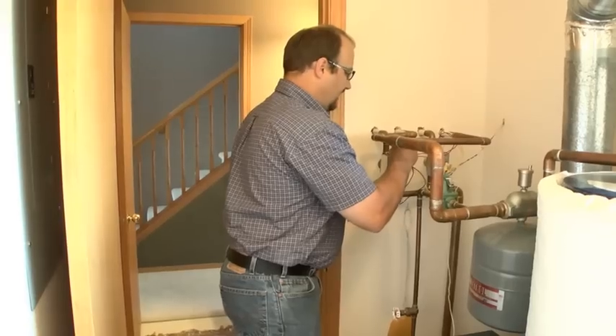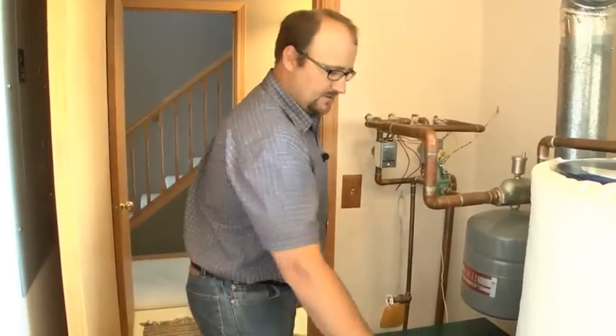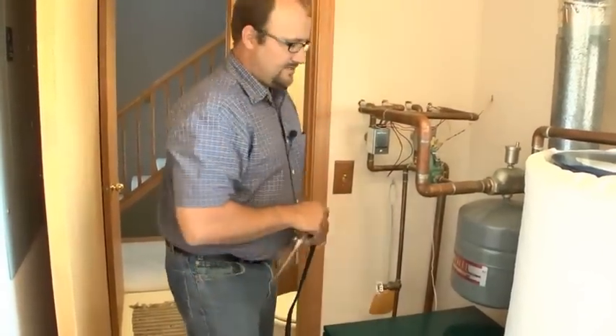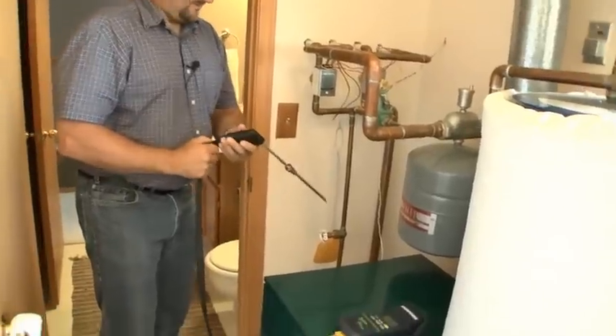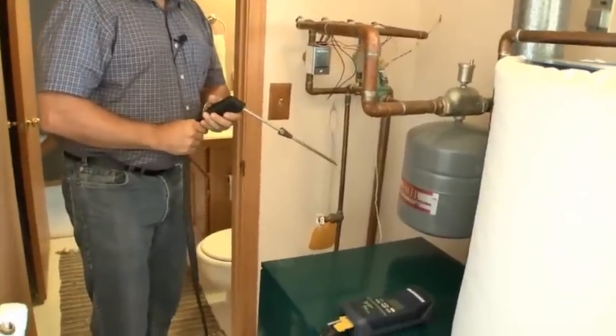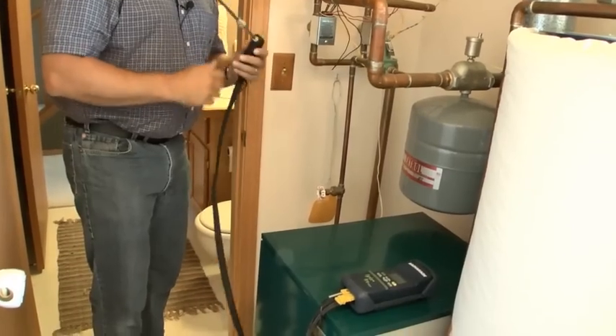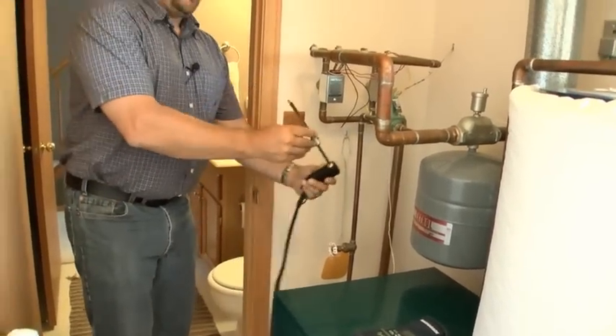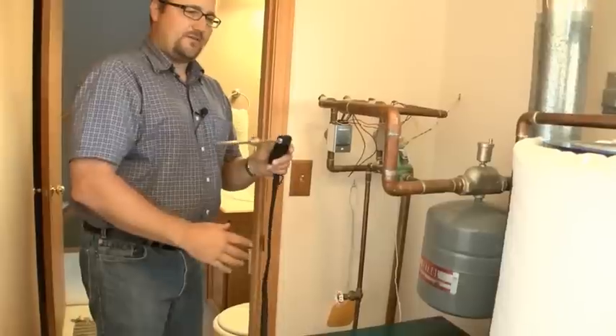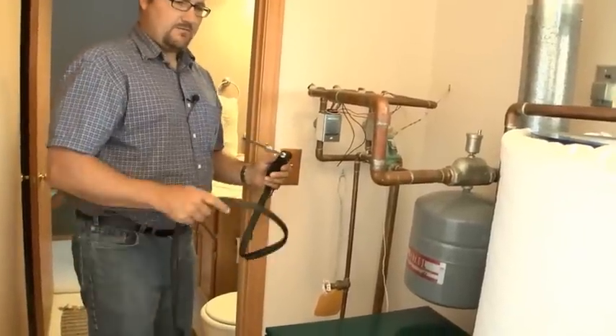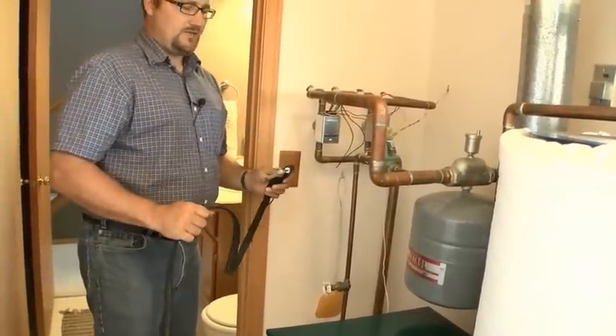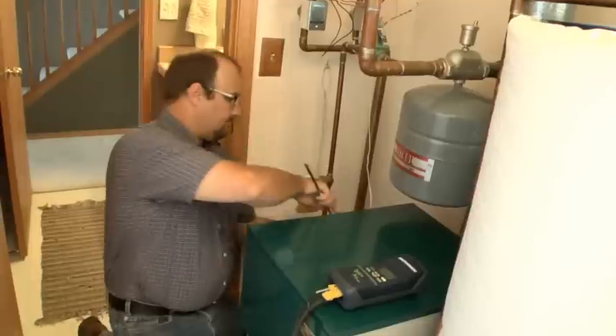And I'm just jumpering the end switch to get this thing to start. This has a draft hood. It's on the back of this boiler. It's fairly difficult to get to. I have to take this probe and get it up inside the draft hood as close to the top of the heat exchanger as I can, so that I don't get a bunch of excess air.